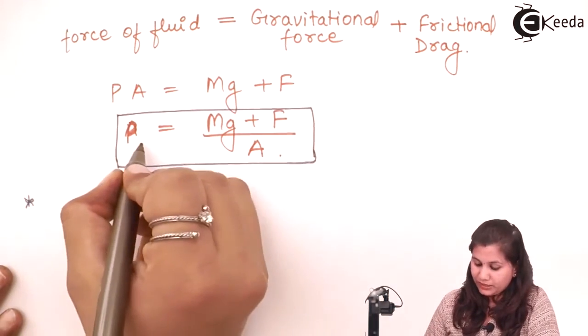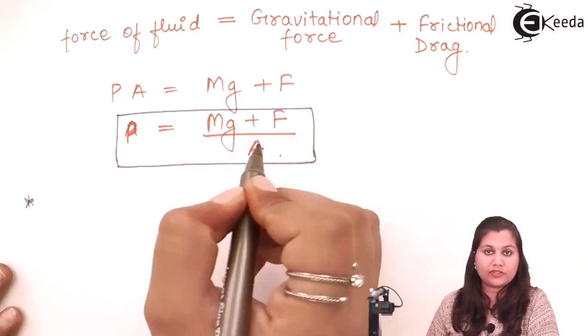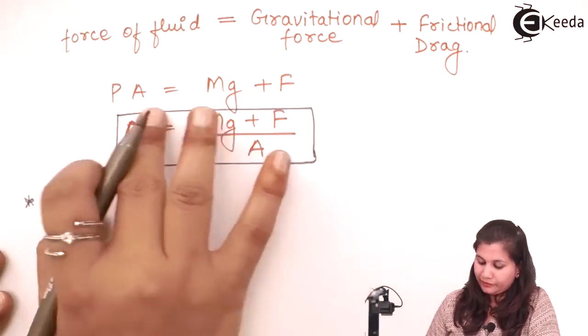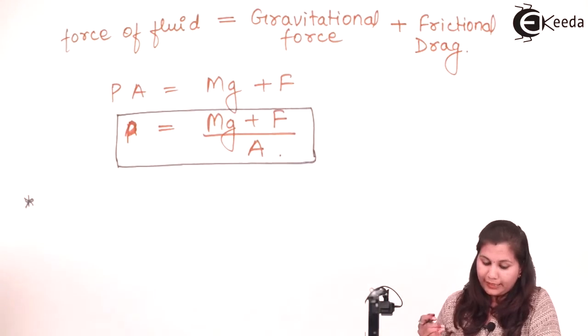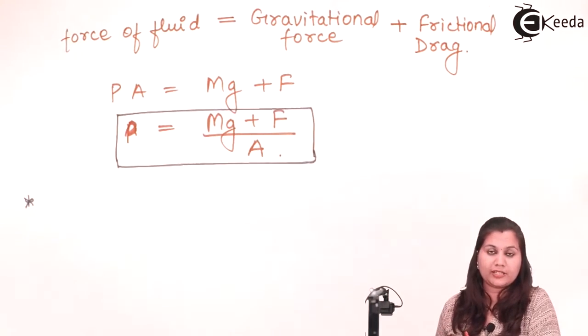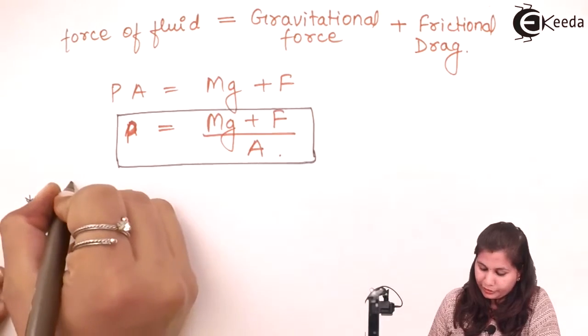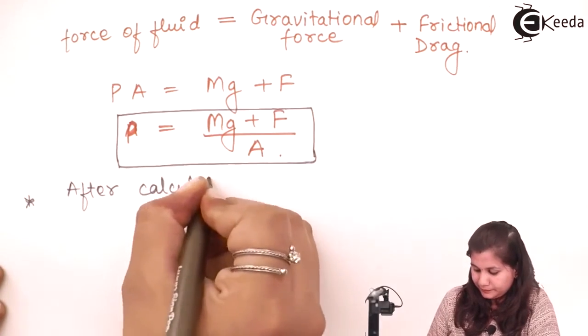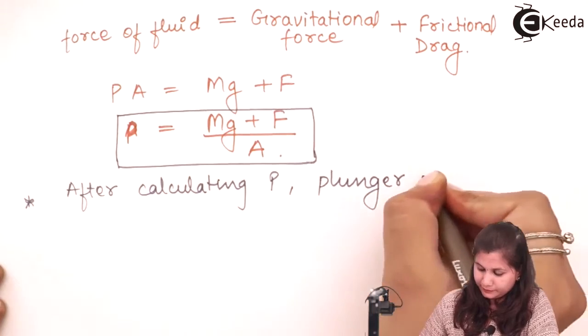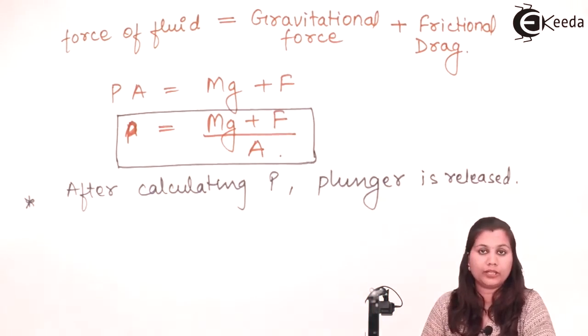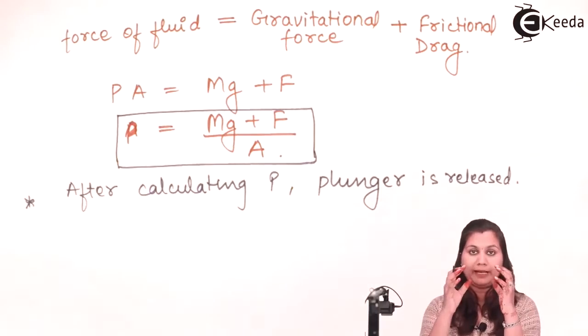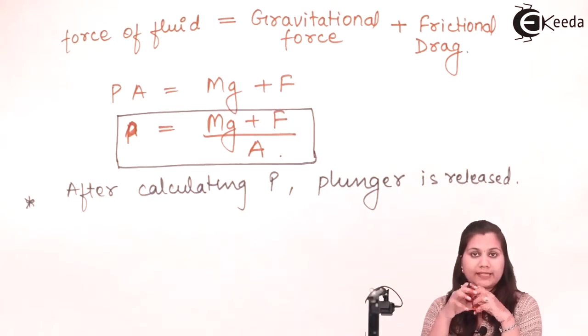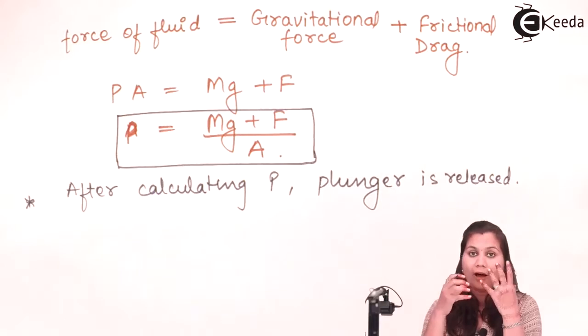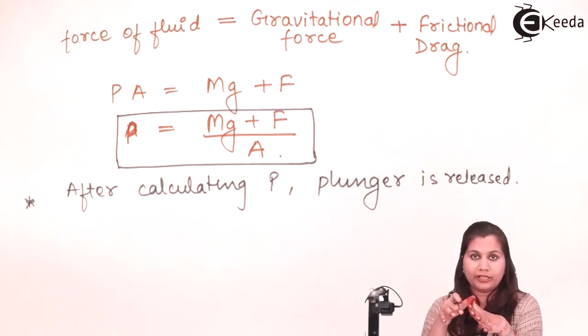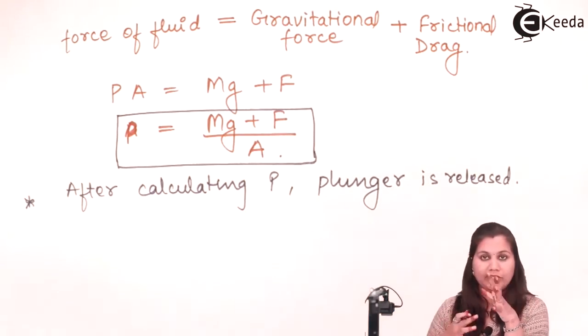So here from this equation we can say that pressure is caused due to the weights which are placed on the platform, and we have calculated that. Now for calibrating the pressure gauge which we are testing here, after calculating P, first what we have done is that we have applied a known amount of weight over this dead weight tester, and we have calculated how much pressure that known weight has generated in the dead weight tester. Now after calculating the P, we have released the plunger.